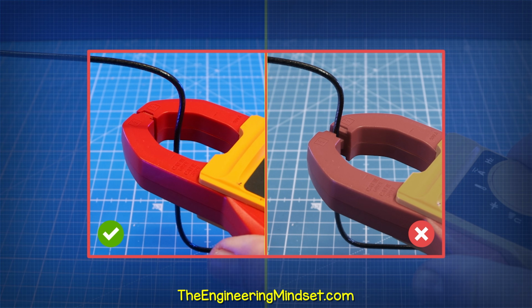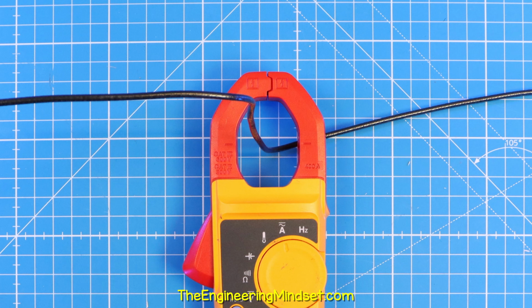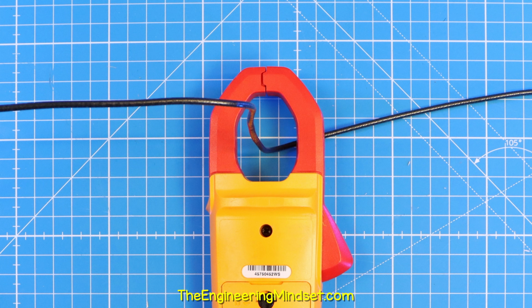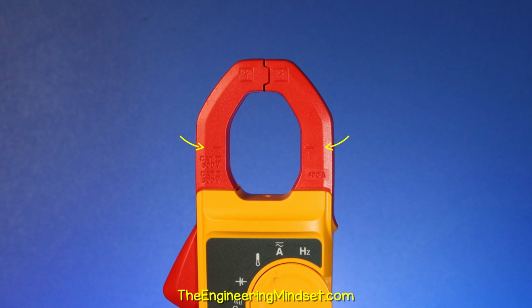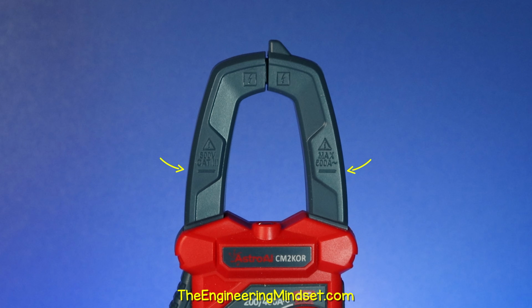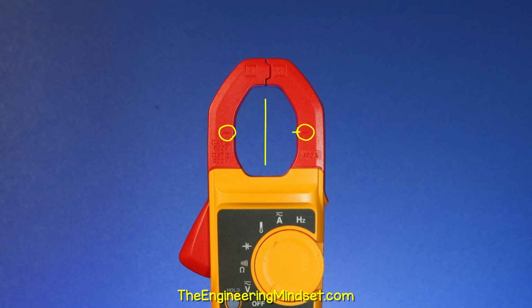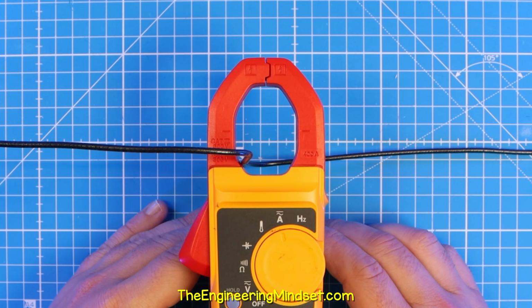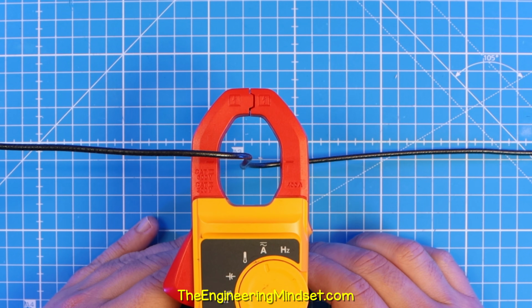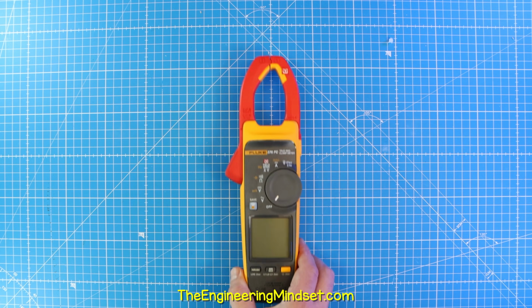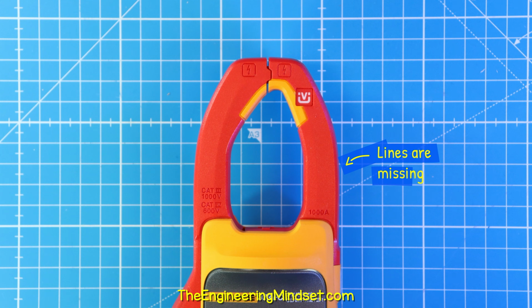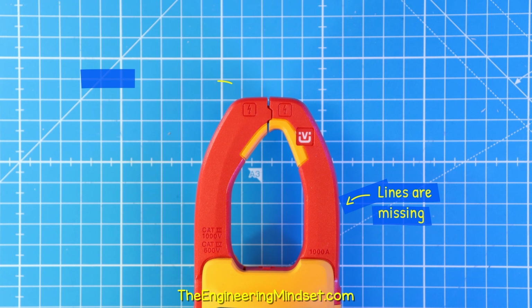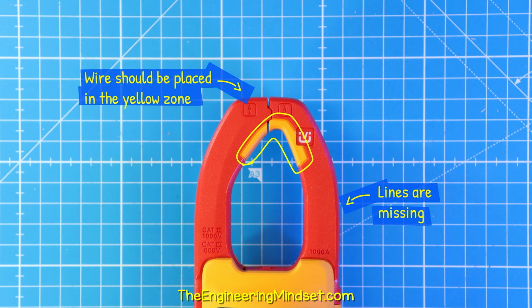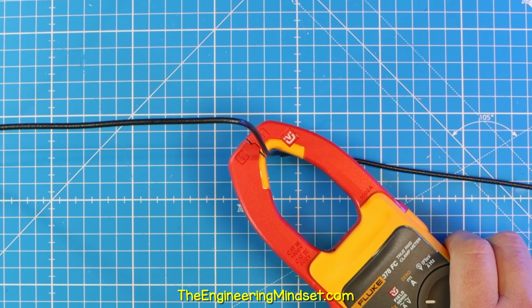Do not clamp the wire between the tips. With AC, it doesn't matter if we connect the clamp this way or this way, the value will be the same. Notice these lines on the clamp jaws. Almost every meter has these. They indicate the center point. Try to keep the wire between these points for the most accurate reading. However, you'll notice that this clamp doesn't have these lines. The wire should be placed in the yellow zone as close to the opening as possible.